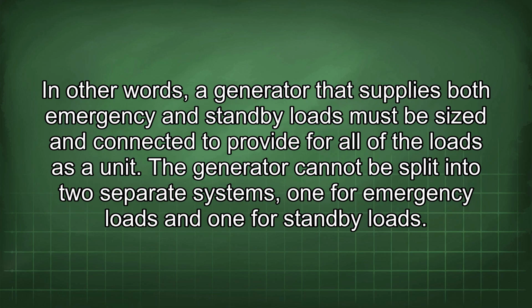In other words, a generator that supplies both emergency and standby loads must be sized and connected to provide for all of the loads as a unit. The generator cannot be split into two separate systems, one for emergency loads and one for standby loads.